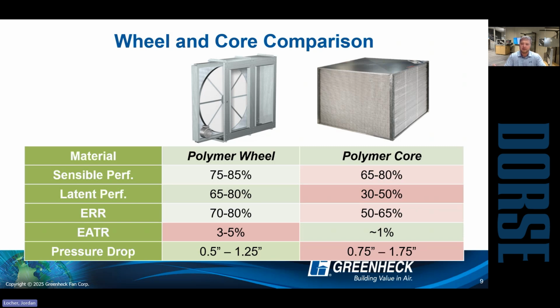So if you are in a higher moisture environment, that wheel is going to provide significantly more recovery. The other big differences, so EATR, that stands for exhaust air transfer ratio, right? That is commonly called cross leakage, or how much leakage you can expect on the device. Wheels, it's common to expect around 3 to 5% leakage. So this is slightly higher than a core. Cores are typically 1% or less.